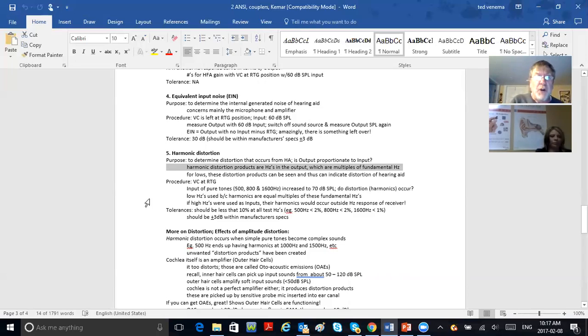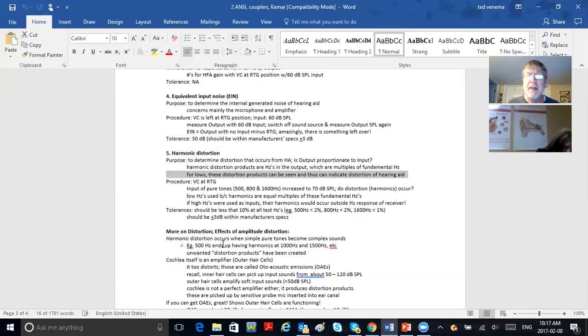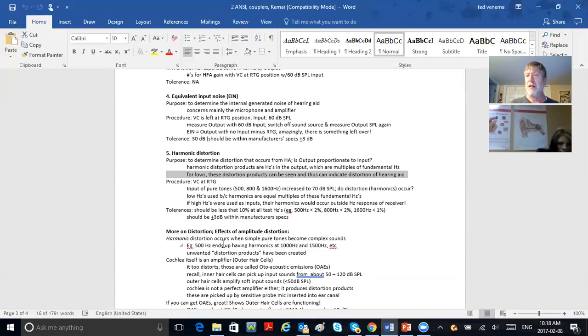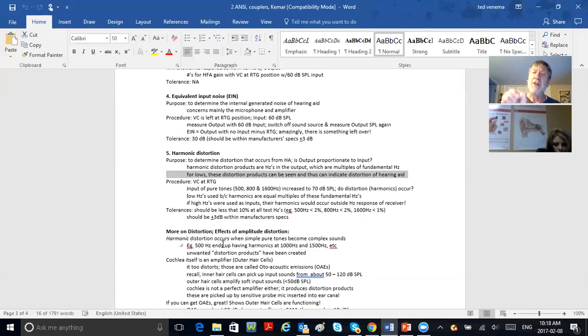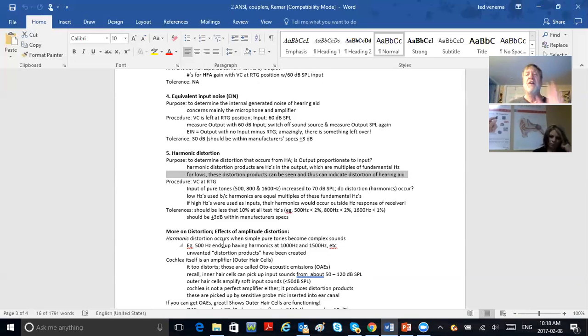For low frequencies, these distortion products can be seen and can indicate distortion of the hearing aid. We say low frequencies because if you tested at 8000 Hz, the next harmonic would be 16,000 Hz—outside the range of all the equipment. So they use low-frequency inputs—500, 800, and 1600 Hz—so that their harmonics are still readable well within the range of the hearing aid.